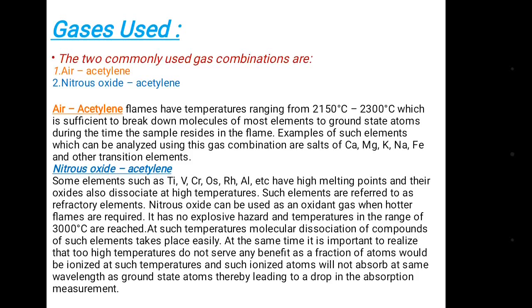At such temperatures, molecular dissociation of compounds of refractory elements takes place easily. At the same time, it is important to realize that too-high temperatures do not serve any benefit, as a fraction of atoms would be ionized at such temperatures and those ions would not absorb at the same wavelength as ground-state atoms, thereby leading to a drop in the absorption measurement.